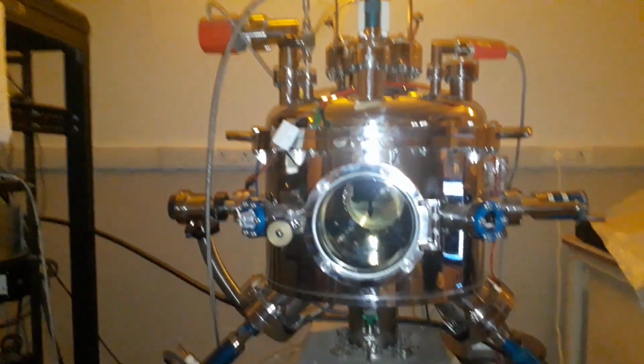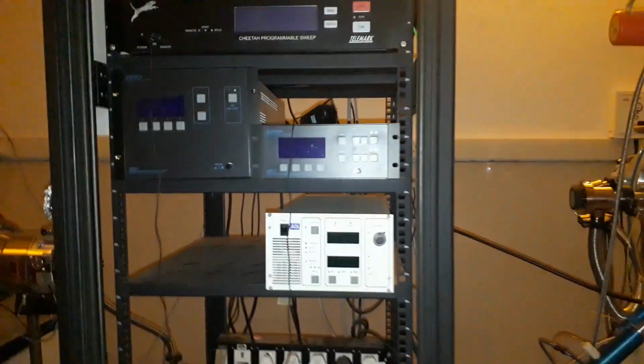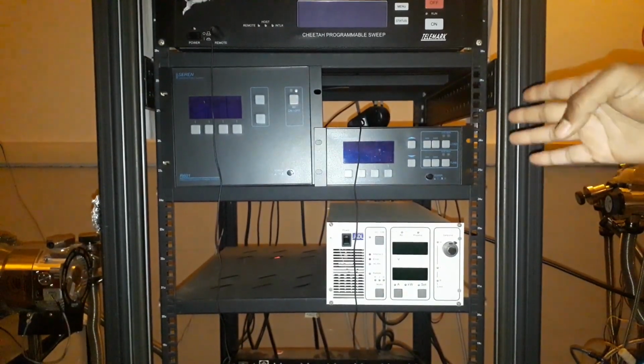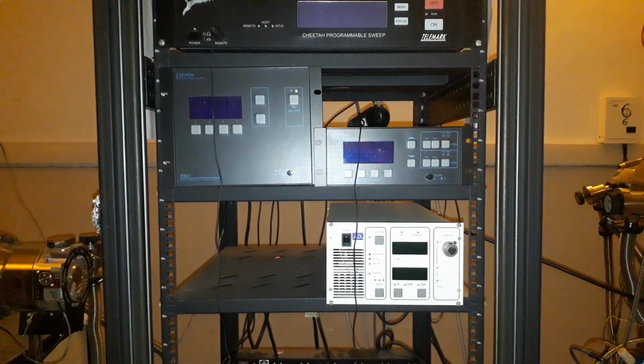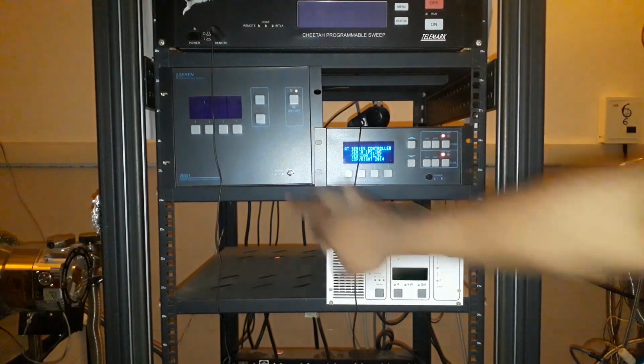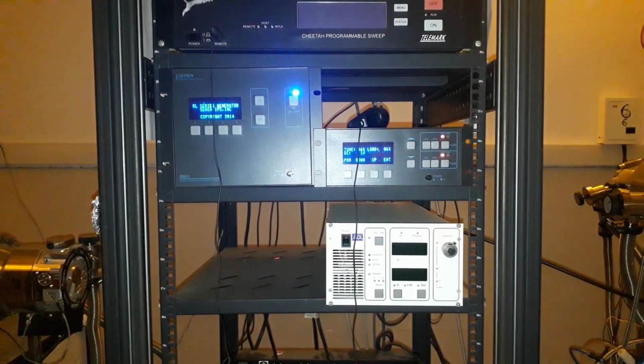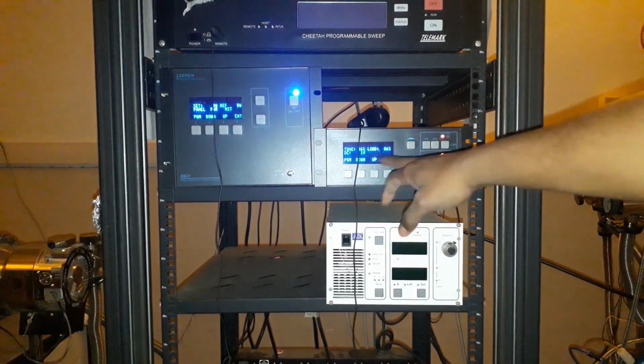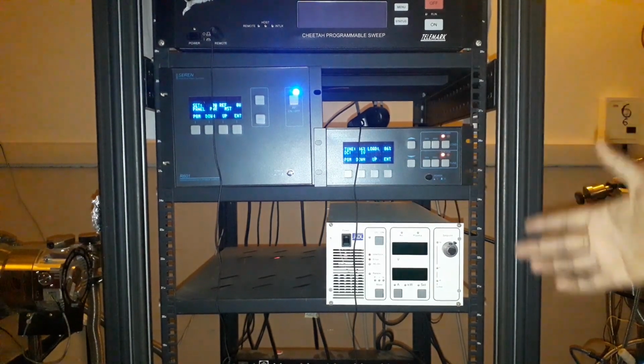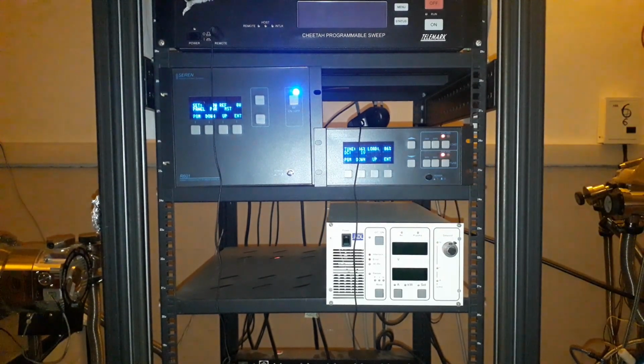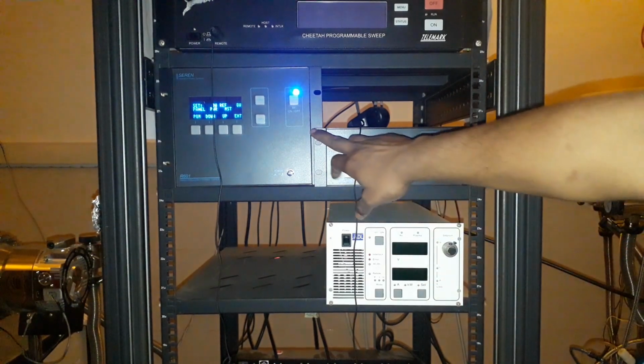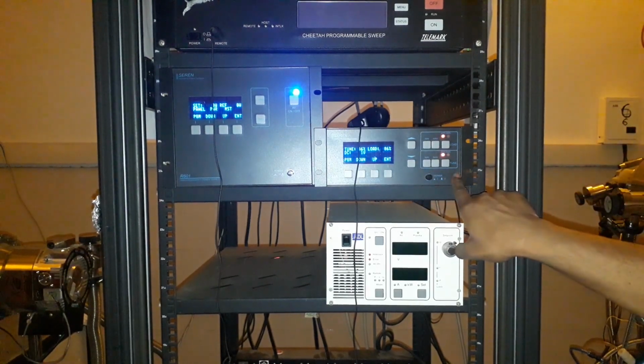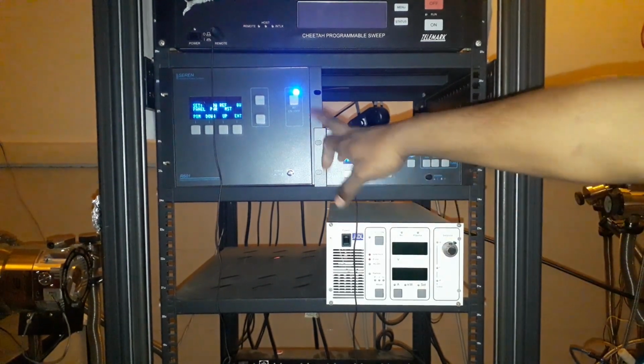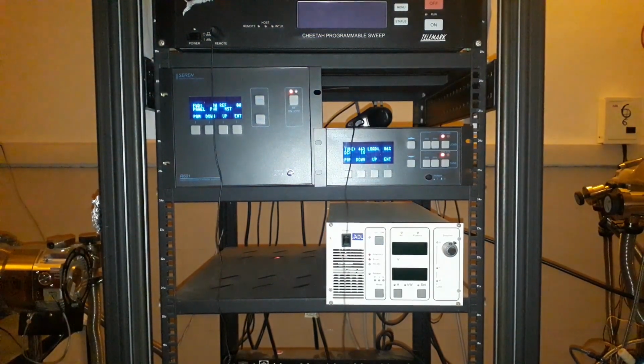Sputtering. So what I'm going to do is move towards the Seren power supply. This is the matching network, and this is the main power supply. I'll turn both of these on. It takes some time to start. Okay, it's fine. This is saying you can do the tuning manually or auto, whatever you want. DC is 1 volt bias. Bias will let us know what is happening. Right now it is in auto mode, so I don't have to do anything. I'll turn on RF. I have turned on RF.